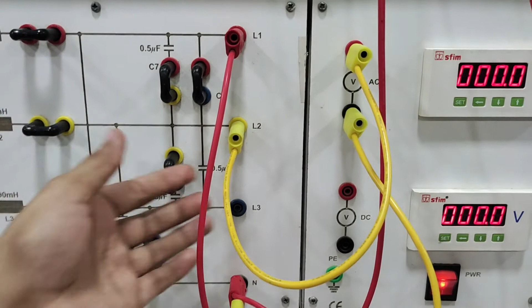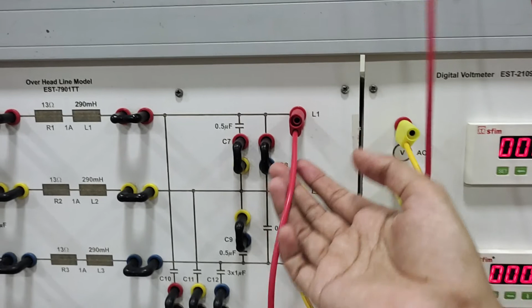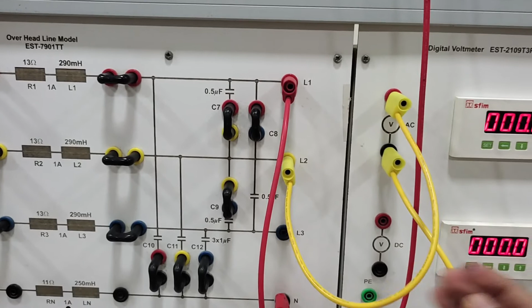So in the procedure, students, we have to measure the voltage for L2 and L3, that are our healthy phases. I have also connected this towards L1, because we can see that in order to measure the voltage for the short circuit phase, you will see that voltage will appear 0. So we can move this connection to L1, L2 and L3, and the voltmeter is connected in parallel. You can see here that this point is connected to the neutral, and here it will be connected in parallel with the transmission line phase. For each phase we can move this point. In order to measure the voltage for L1 phase we will move it here, then for L2 we will move it here, and in order to measure the voltage for L3 phase we will connect this point to here. So students, this is the whole circuit.